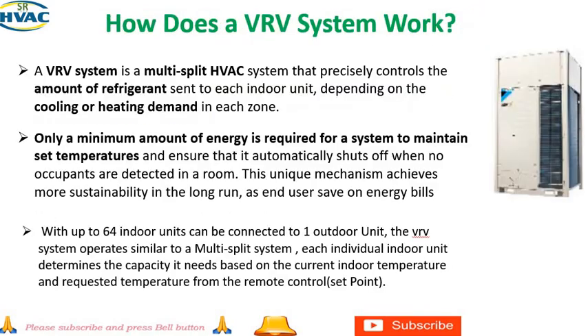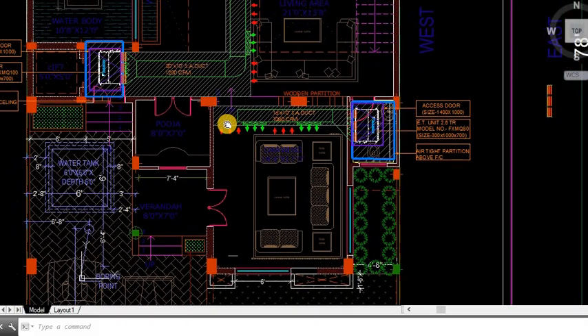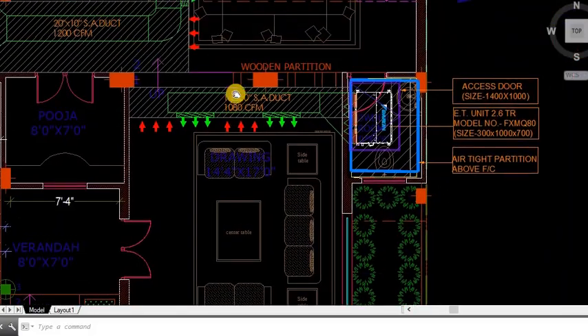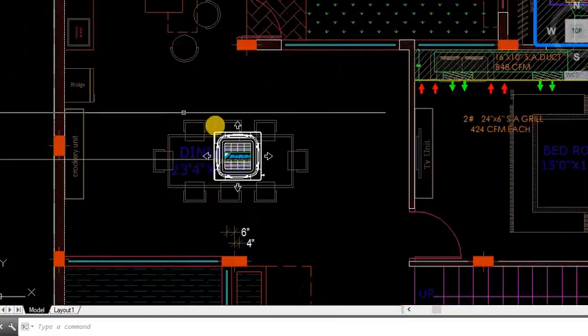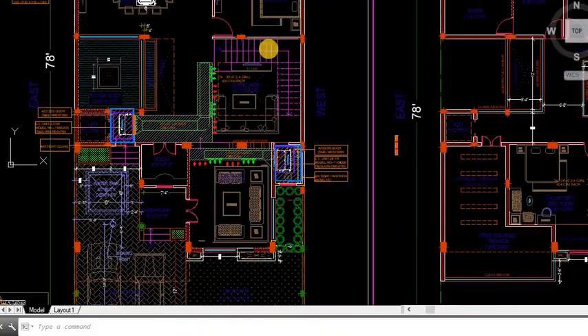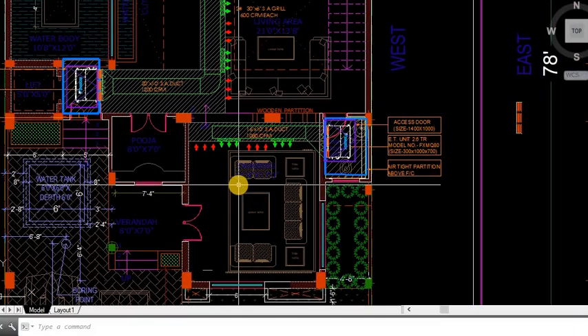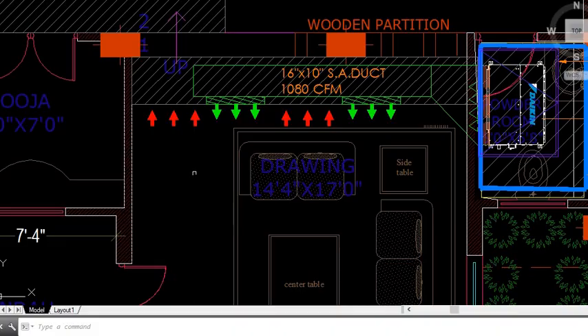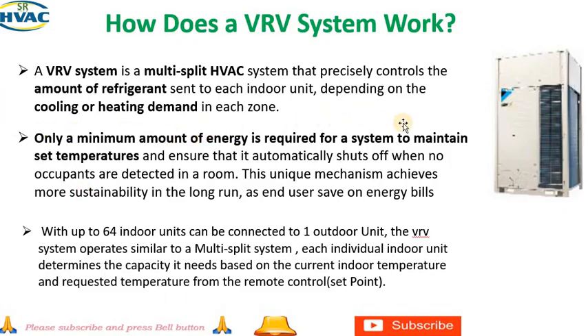Next we will see how a VRV system works. A VRV system is a multiple split HVAC system that precisely controls the amount of refrigerant sent to each indoor unit depending on the cooling or heating demand in each zone. Friends, if in a home there is a particular requirement in a particular area, it will give heating or cooling to that zone only. Suppose this is the dining area, nobody is here. In the bedroom, nobody is here, but people are sitting in the drawing room or living room. It will supply the refrigerant to this zone or area only. This way you can save on the energy bill. Only a minimum amount of energy is required for the system to maintain the set temperature. It ensures the unit automatically shuts off when no occupant is detected in the room. There are sensors which can detect whether an occupant is there or not. This unique mechanism achieves more sustainability in the long run, as the end user will save on the energy bill.